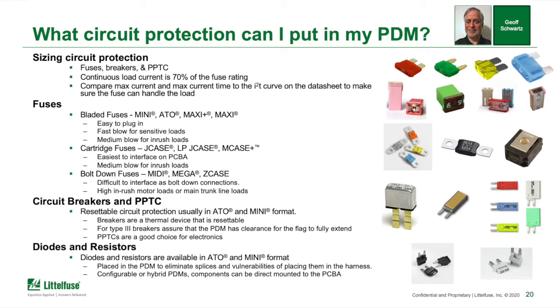Type 3 breakers. If you're going to use a Type 3 breaker in a PDM, you need to make sure that the cover and the top of the flag on the Type 3 breaker clears the cover. Because if in fact it does not, you can actually get it at a point where you don't get full break if the flag is not allowed to come to full extension.